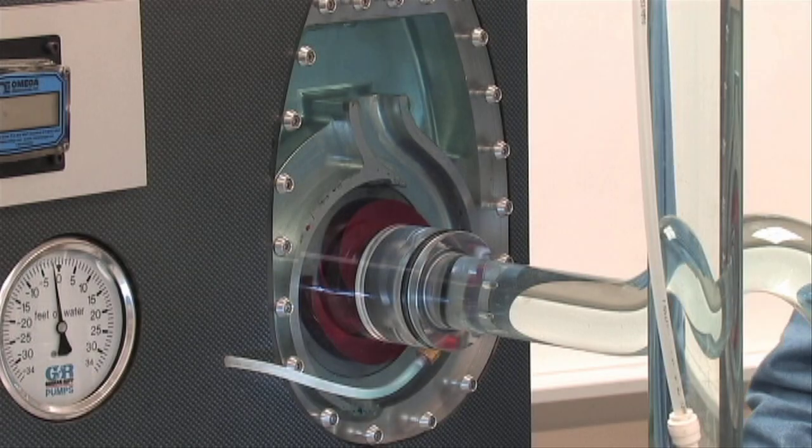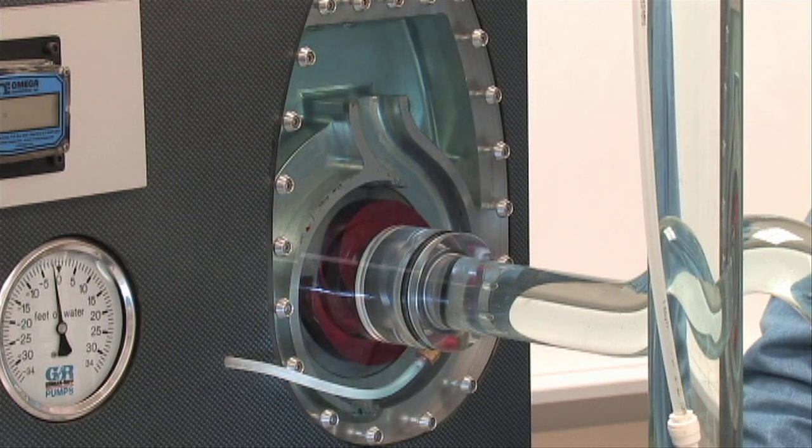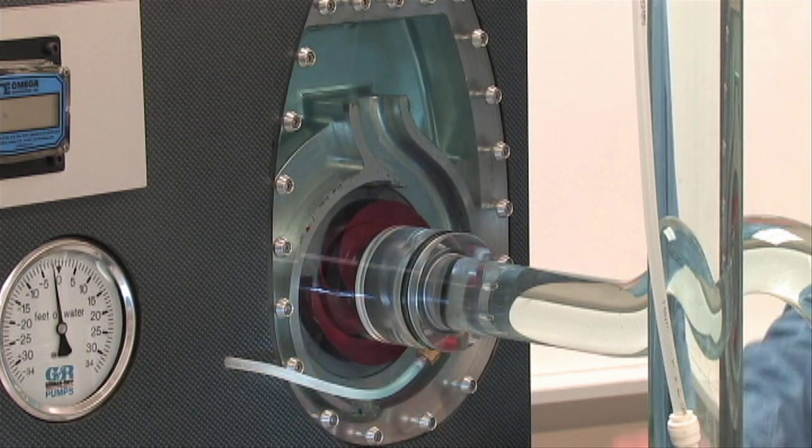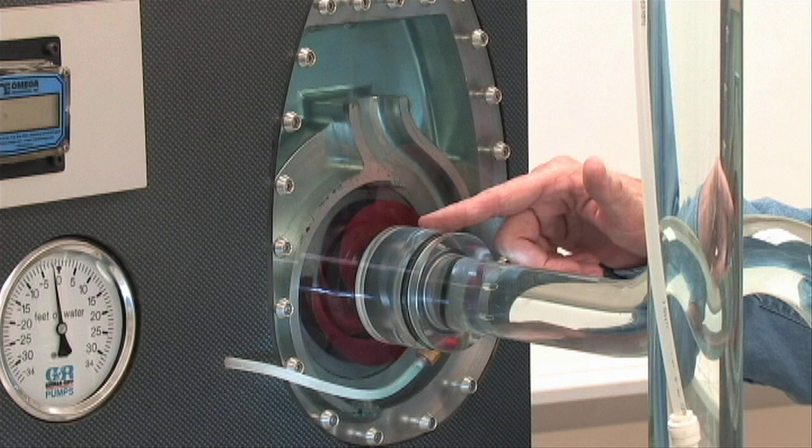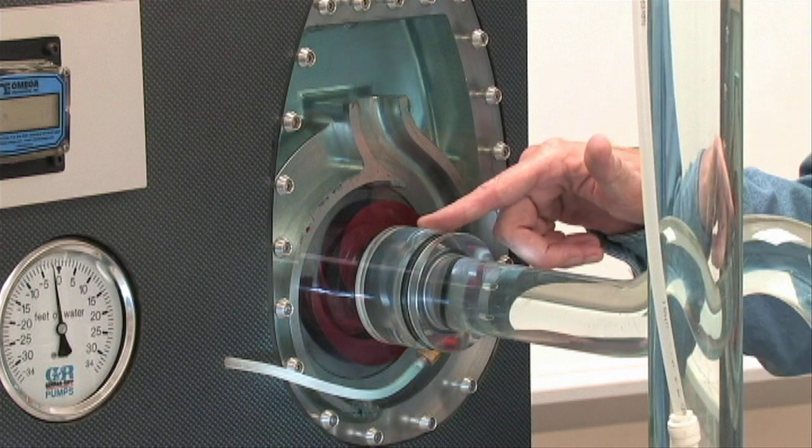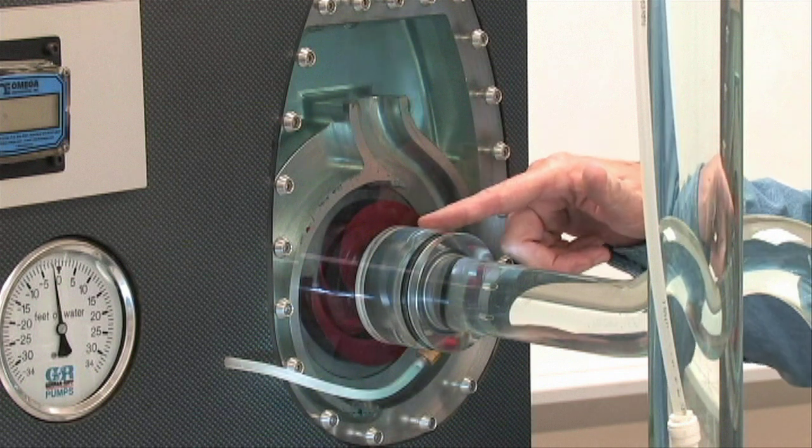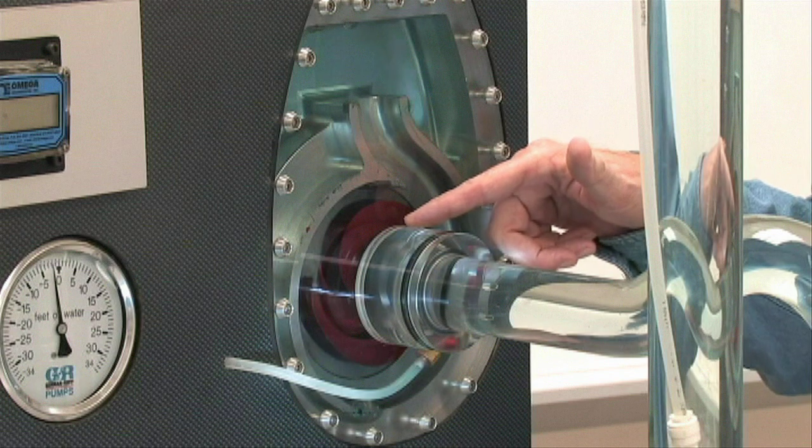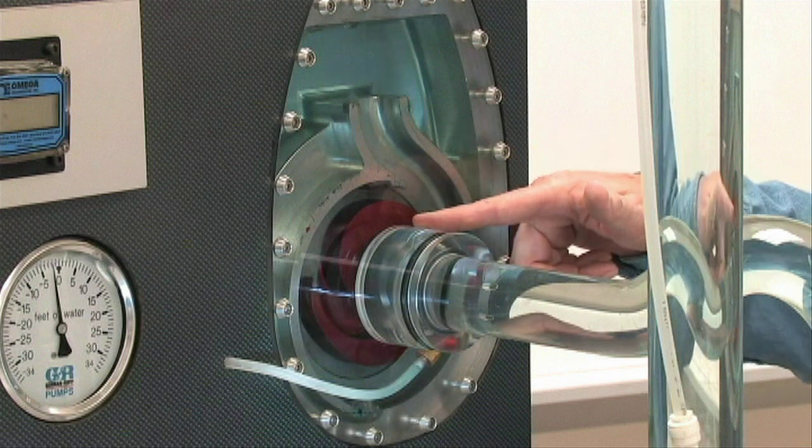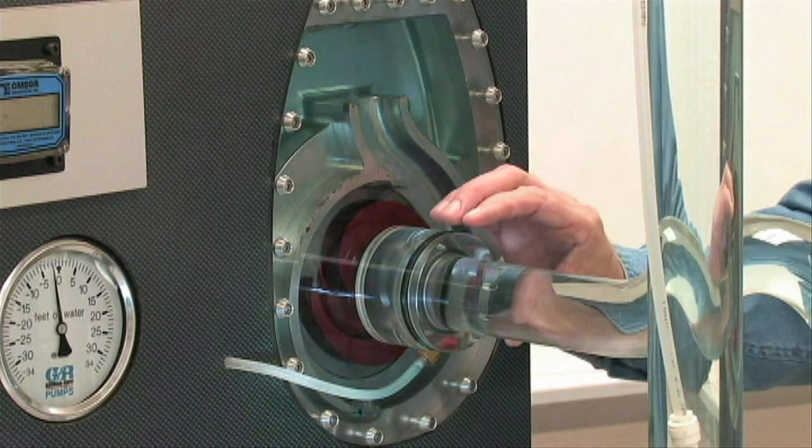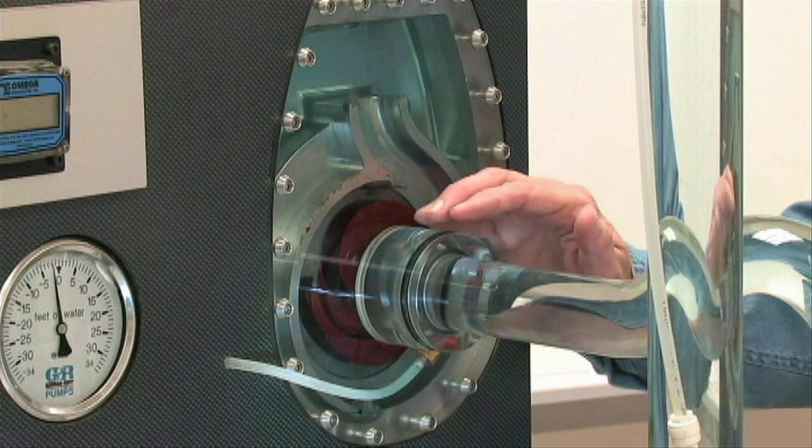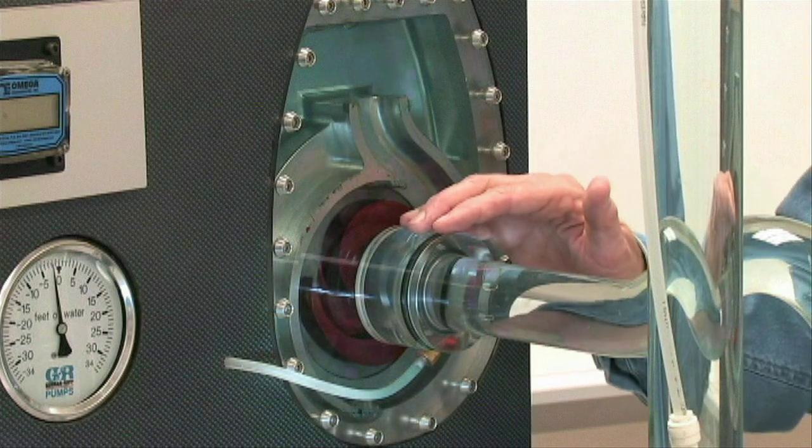Some other causes for failure to prime that cannot be demonstrated with the glass face pump include face clearance. The greater clearance between the impeller and the wear plate, the less vacuum created by the pump. This can also be caused by wear. Another cause could be a plugged eye. If you plug up the eye of the impeller with debris, it removes all the hydraulic capability of the impeller.